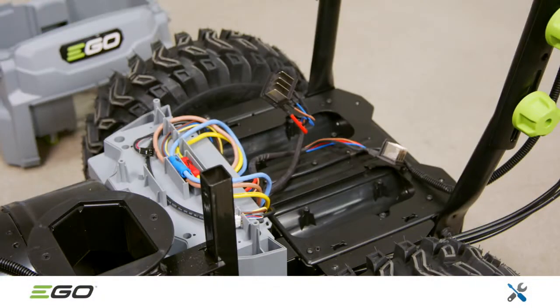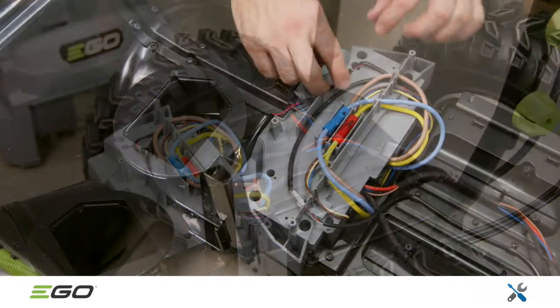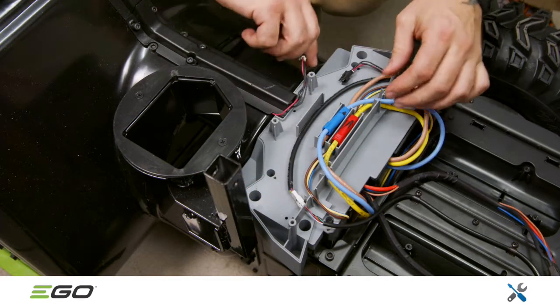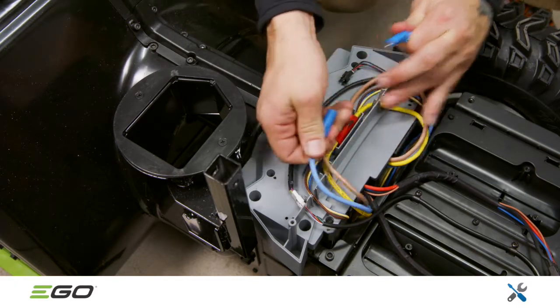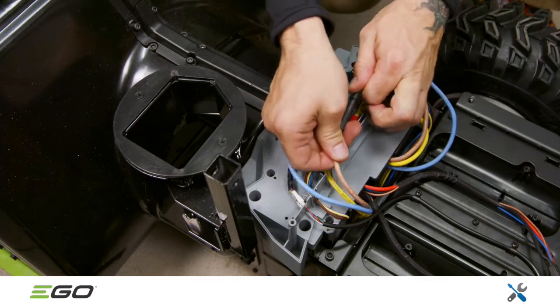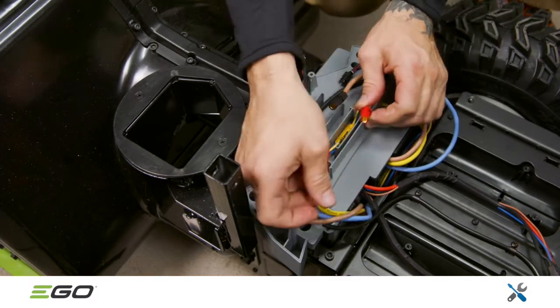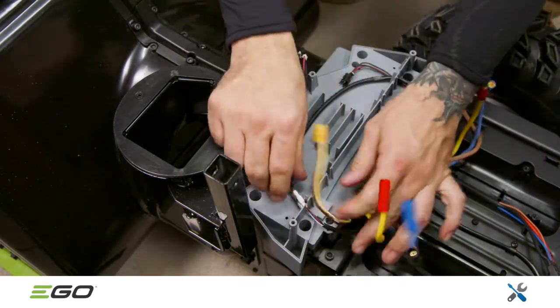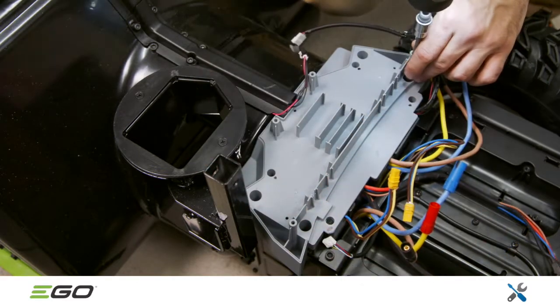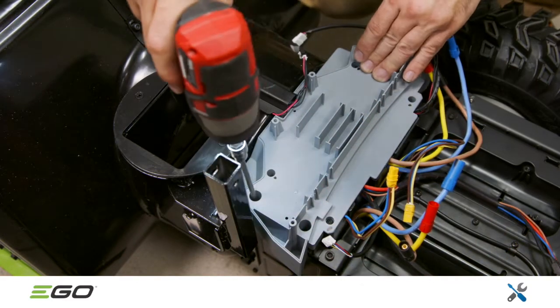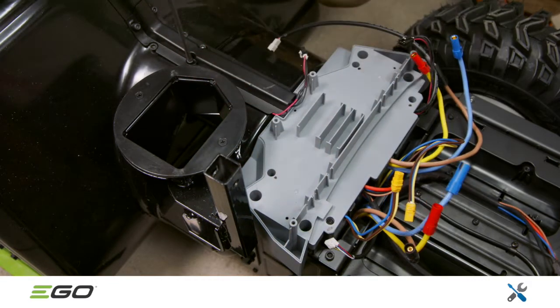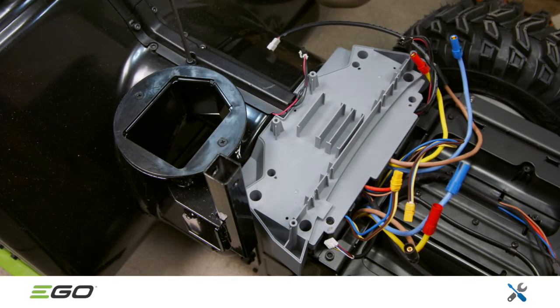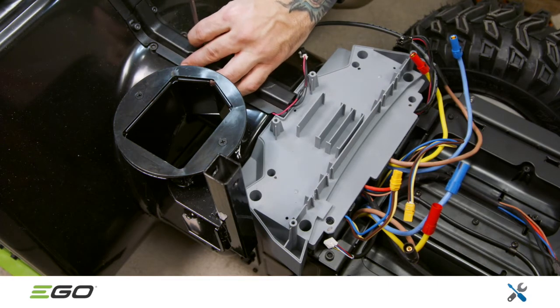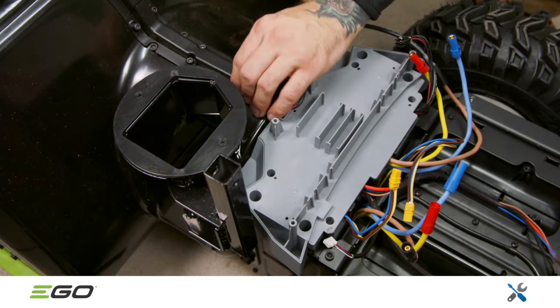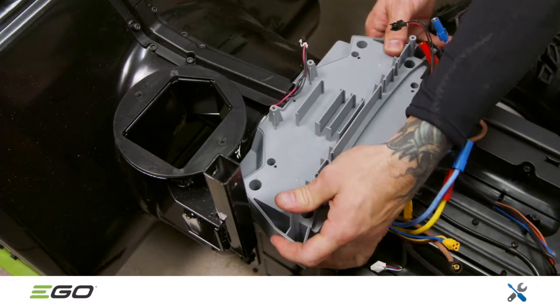To replace any of the PCBAs, start by removing the battery box as previously shown. With the battery box removed, disconnect the 6 plugs. Next, remove the 4 5mm hex bolts that secure the PCBA assembly. Then loosen the 2 4mm hex screws that secure the adjacent wire cover. The PCBA assembly can now be removed.